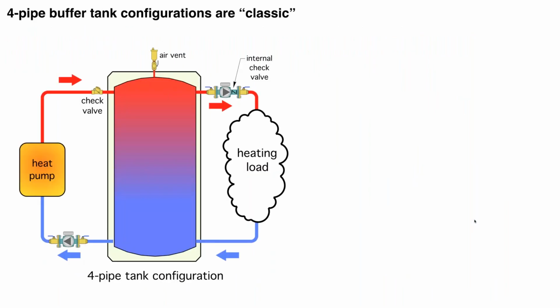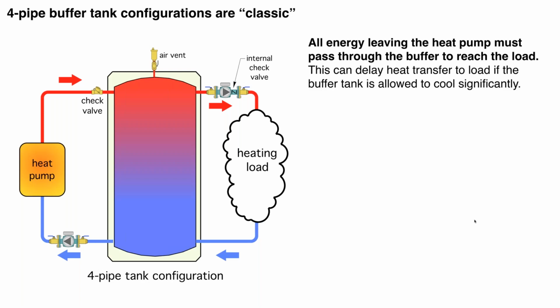So let's look at a 4-pipe in more detail. All the energy that leaves the heat pump must pass through the buffer tank to reach the load. There's no way around that, okay? If the buffer tank is cool, let's say the heat pump's been off for some reason, for several hours or perhaps 2 or 3 days, to get heat out to the load, we're going to have to first warm some of the mass within that tank. Now, when it's piped like this, it's true that the warmer water will tend to stay near the top of the tank and go across here, but there's always going to be some mixing occurring here, okay? And that is going to represent a delay in getting the temperature to the distribution system the same as the temperature coming out of the heat pump, okay?